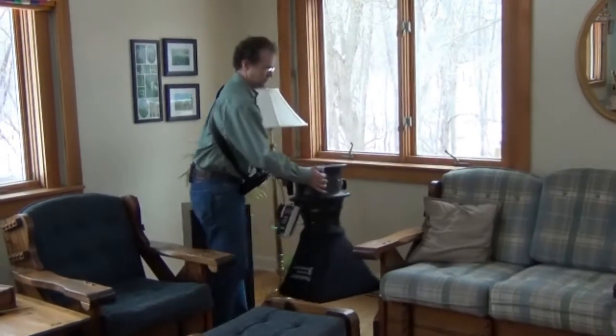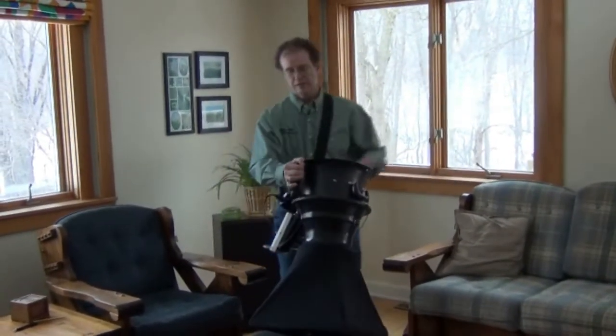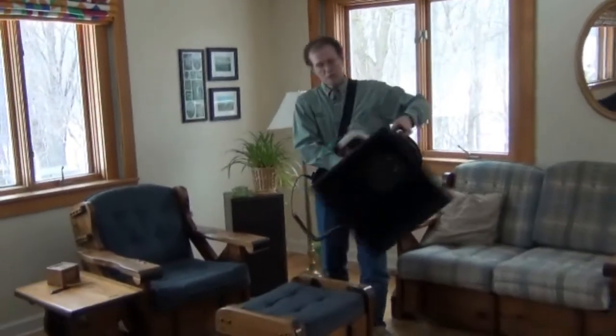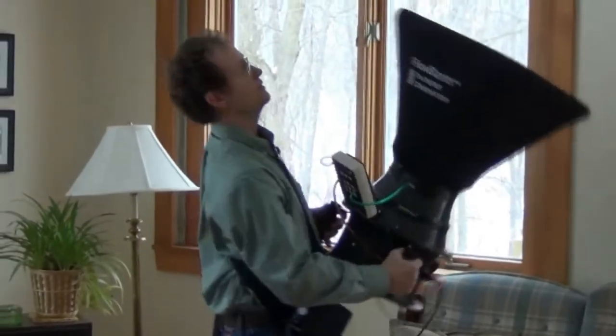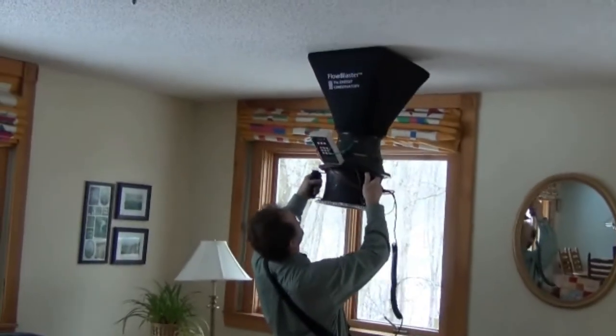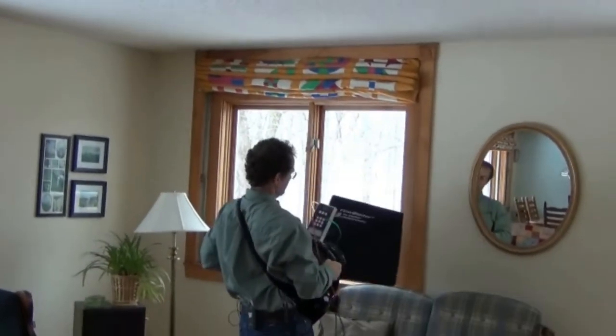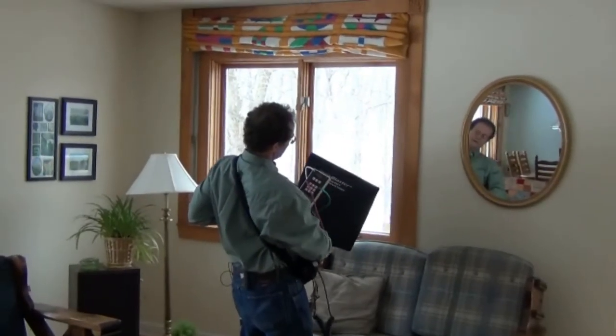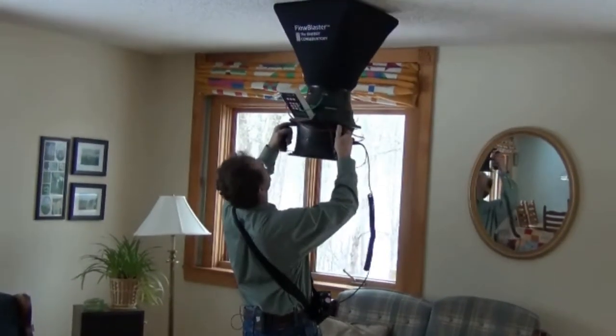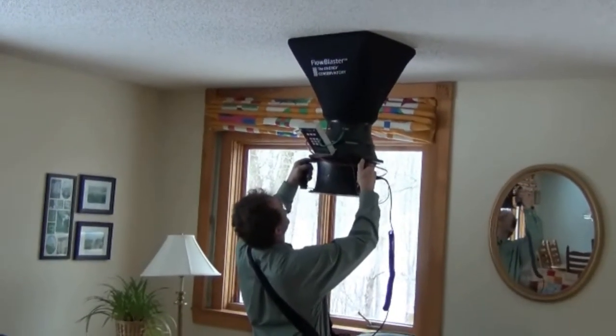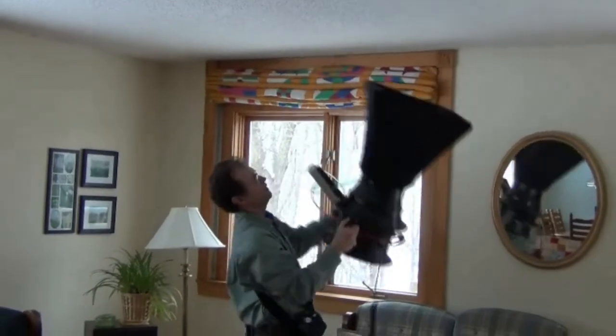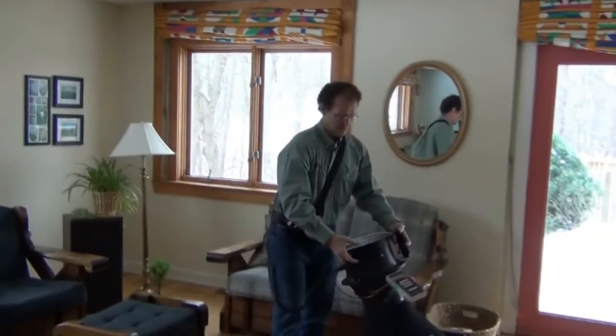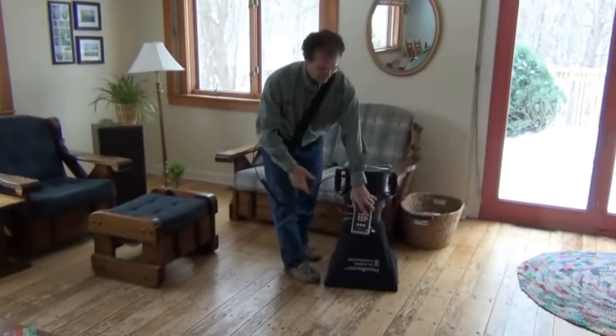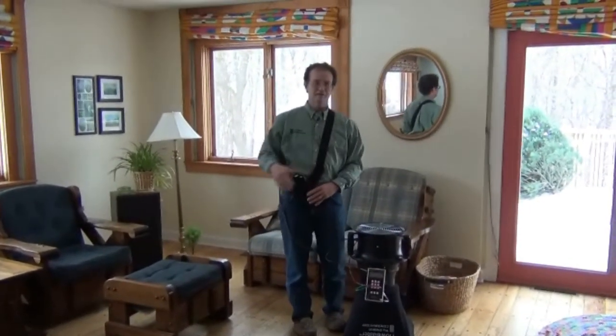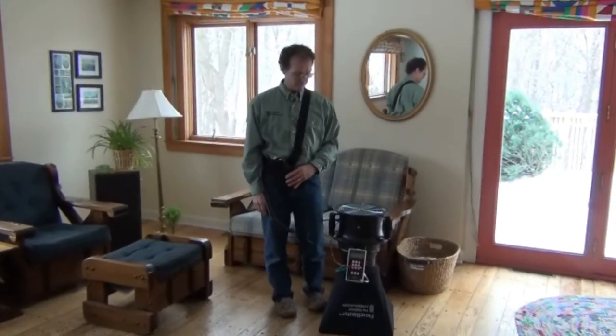And if you're using it to measure ceiling registers, you can turn the gauge around the other way so you can see it better. You can tilt it down so you can get a reading. You can hit start fan while it's down here, and then once it senses the pressure, it'll ramp up, display your measurement, and then you're ready to go to the next one. So that's it. That's our demonstration of the FlowBlaster attachment for the Duct Blaster fan.